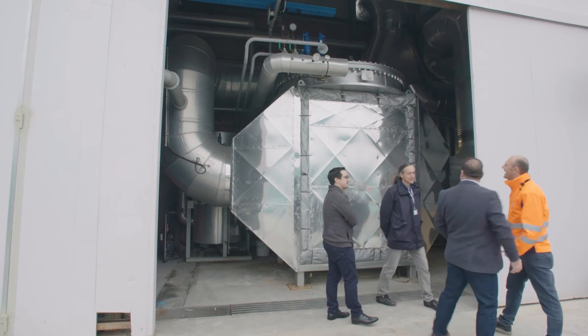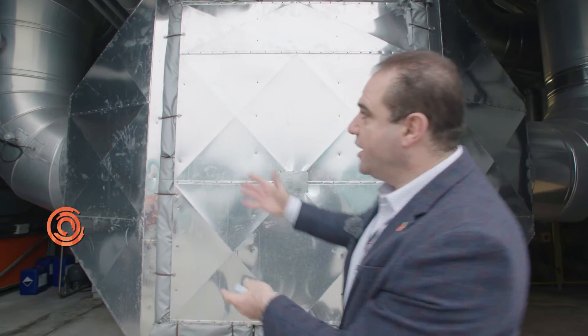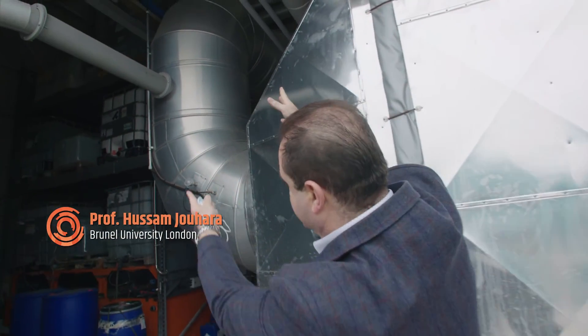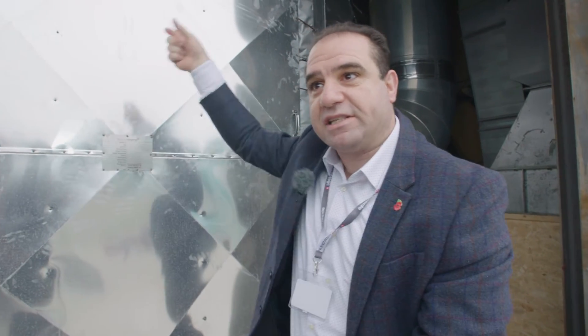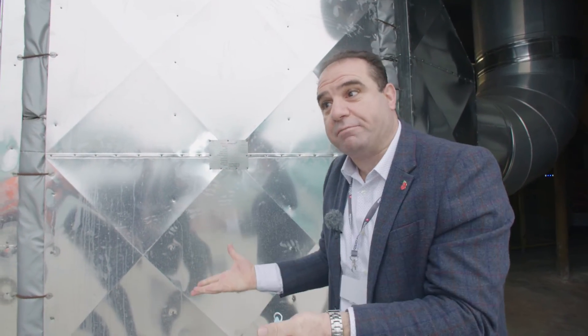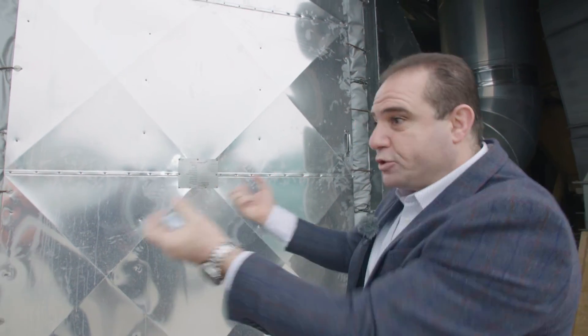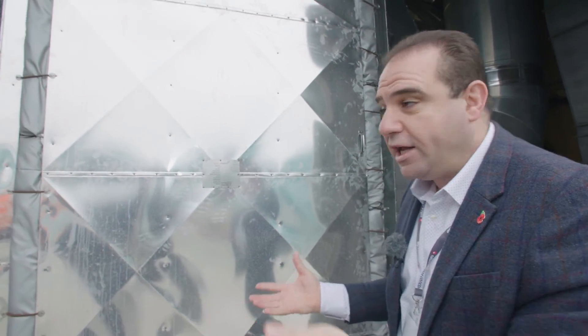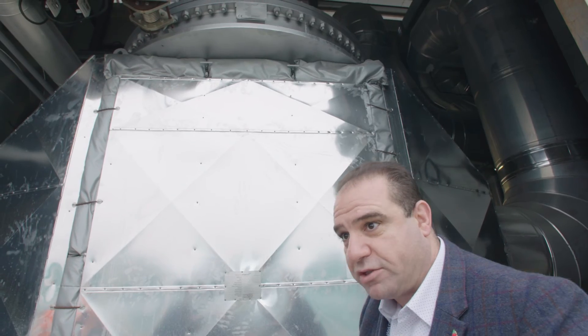The inventor of the Etikina heat pipe heat exchanger technology is Professor Hussam Johara from Brunel University, London. The project aimed at extracting heat in a passive manner from an exhaust flow coming from the process inside the factory. The exhaust goes through the heat pipe heat exchanger, where heat pipes are staggered in a certain configuration to absorb heat passively. The heat is then delivered to the shell, which heats water flow to high temperature for use in various areas. The unit absorbs 700 kilowatts — about 0.7 megawatts — delivering this heat to water directly used in the company, reducing fuel use and improving environmental status by reducing emissions.